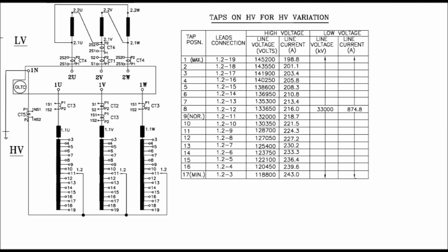198.8 ampere. When the lead connection is taken at position number 11 in the tap winding, then the nominal tap will be selected, that is 9 number tap position will be selected, and therefore the line voltage is nominal line voltage, which is 132 kV, and line current is 218.7 ampere. Again, by increasing the tap position from 10, 11, 12, the selector position, that is 1.2, shall be changed from 11 to 10 to 9 to 8, and so on.